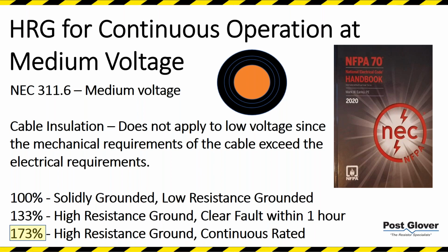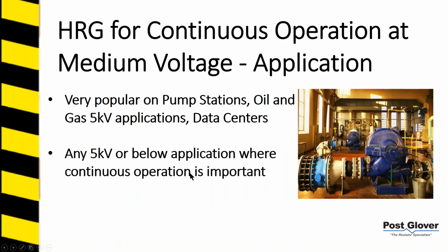So just keep in mind that if you are looking to do a medium voltage high resistance ground system operating continuously, rather than tripping quickly, you might have additional cable costs there, or you will, depending on how long you run. Just from my experience, I've seen a lot on pump stations, oil and gas, 5 kV applications. I've seen a lot on data centers, usually on generators. For data centers, it's both for generator protection, but also for continuity of service at 5 kV. And once again, that's any 5 kV or below application where continuous operation is important.